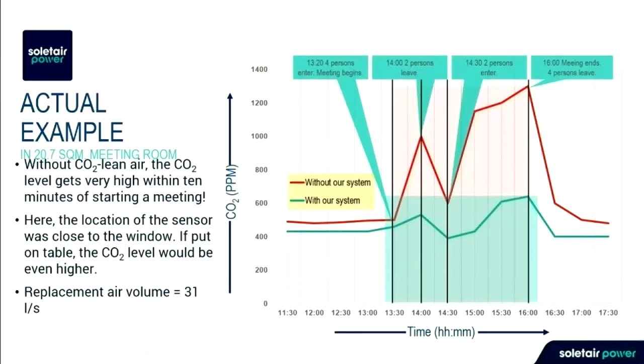If you have a single room system, which we can also offer, you can really keep the CO2 levels low. Here's one example from a single meeting room, in a building built in 2006, so fairly modern. We can keep it below 600 ppm, even though without the system, with the ventilation running, it would go to 1,200. This is a big difference, and you can really feel the change if you have the system at your office.